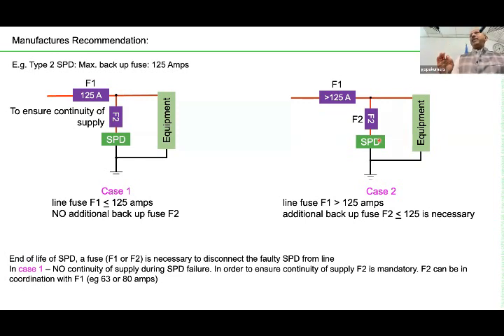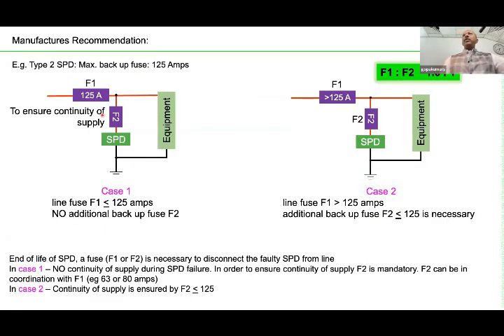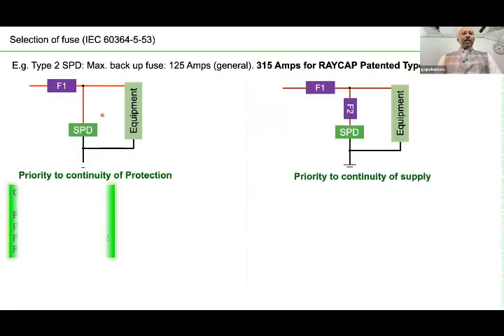To simplify the subject, the user should understand whether he needs continuity of supply or continuity of protection. If you need continuity of supply, irrespective of the line fuse, let's say for example 125 amps, you need an F2 if you want continuity of supply. Otherwise, continuity of supply is gone. So this is very critical to understand. And the rating of the fuses F1 to F2 is 1.6 to 1.